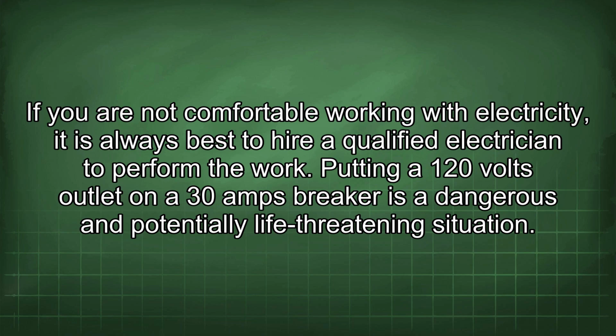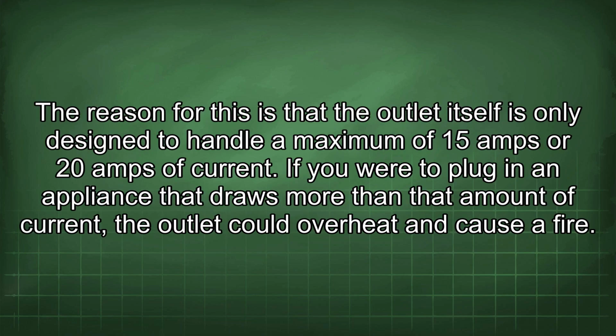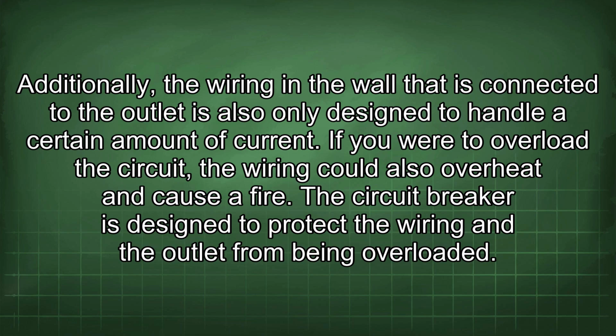Putting a 120 volt outlet on a 30 amp breaker is a dangerous and potentially life-threatening situation. The reason for this is that the outlet itself is only designed to handle a maximum of 15 amps or 20 amps of current. If you were to plug in an appliance that draws more than that amount of current, the outlet could overheat and cause a fire. Additionally, the wiring in the wall that is connected to the outlet is also only designed to handle a certain amount of current.